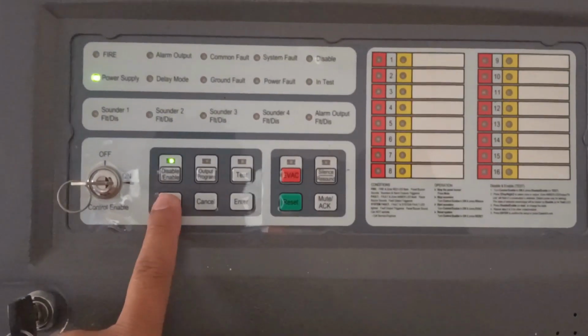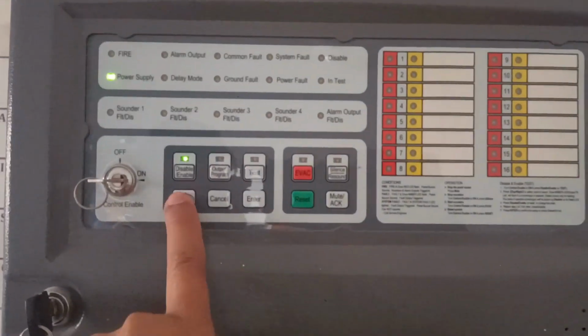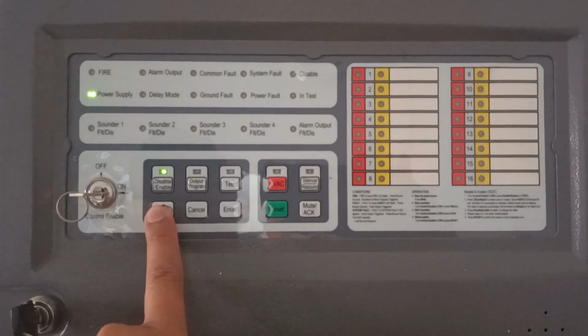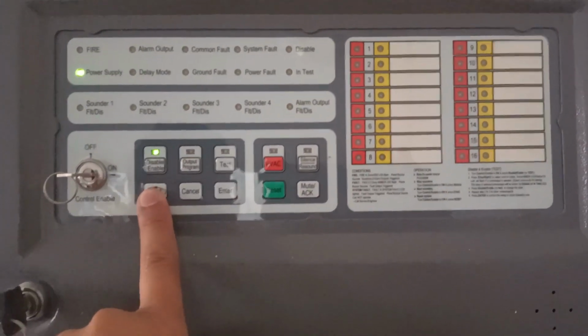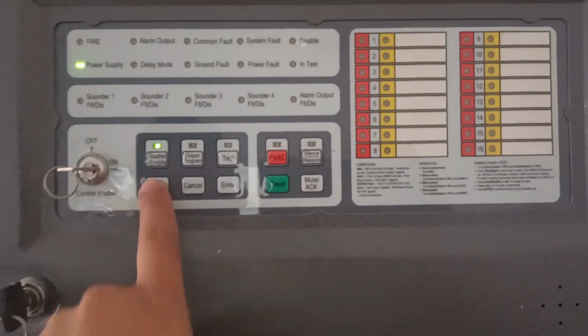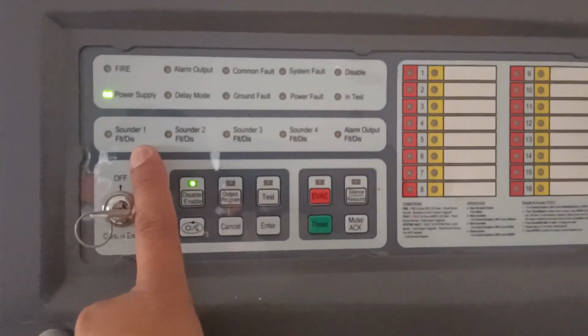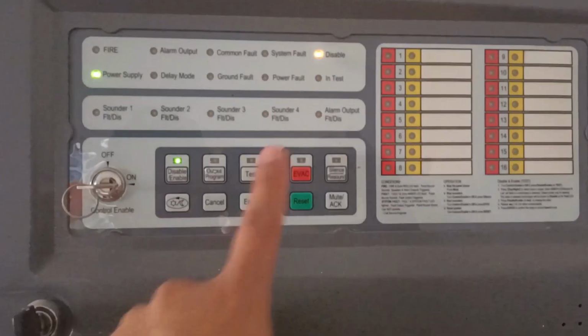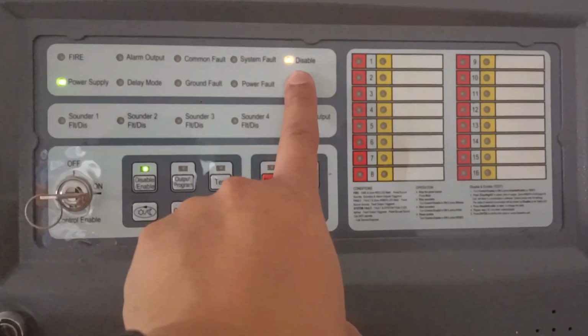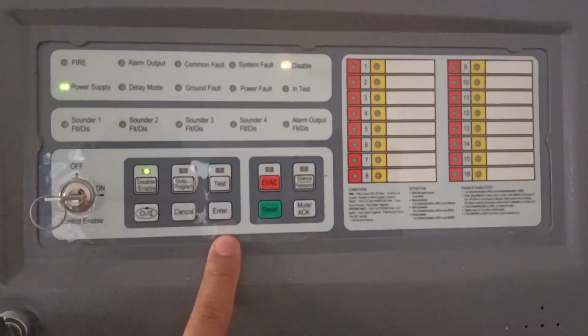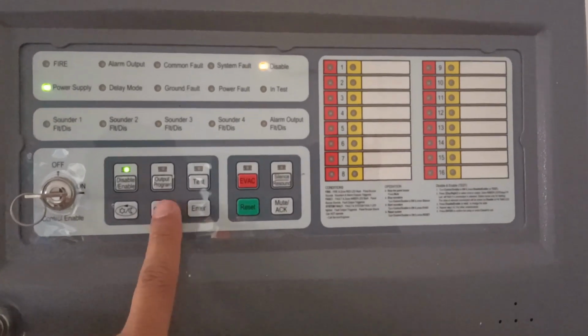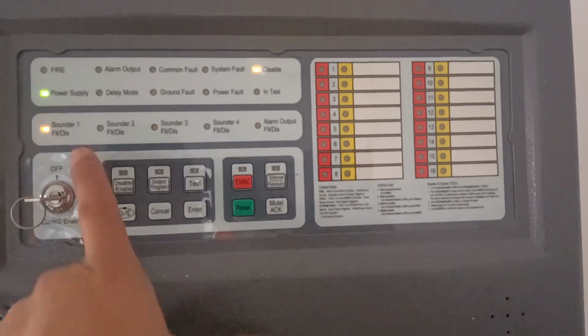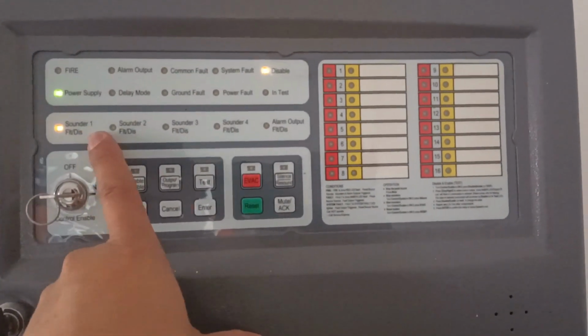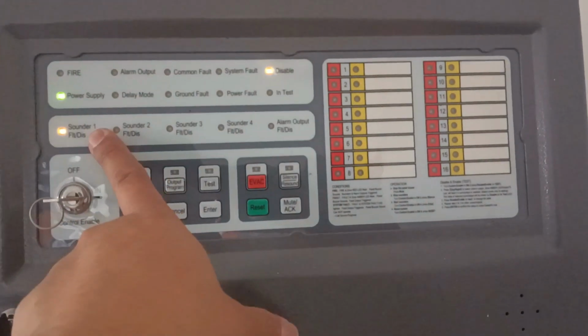You guys, if you want to disable sounders, you must go to disable, then press this button, going down until you come here. So you are going down like this until you come to sounder 1. So this is sounder 1, the line of the sounder one, guys. So you can press disable, the disable light comes on, then press enter, and then cancel. So sounder one is disabled.